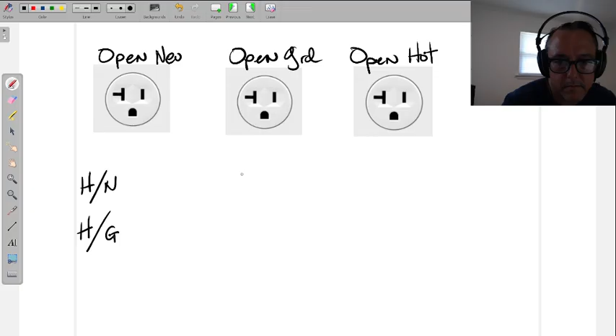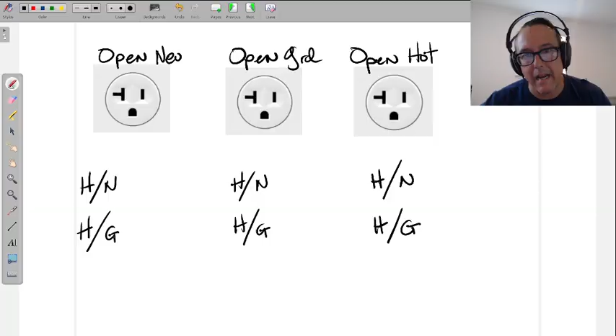And this is why, if you take nothing away from troubleshooting, hopefully you take more than this one thing, but if you take nothing else away from troubleshooting, take this with you. See the problem in front of you. Don't just take someone's word for something not having power. All right? Because people will say a lot, this is not working. That has no power. I plugged in my lamp and my lamp is not working. That has no power. And once you start to just kind of go, well, that has no power, and then you plug in the lamp and you're like, yep, that has no power. All right, let me check to see what happened to the power, and let me go to the breaker. We want to get a visual of what, quote unquote, no power means.